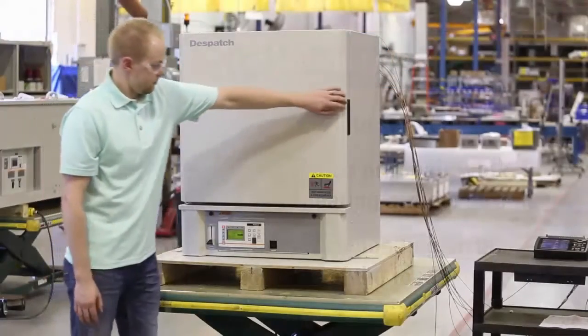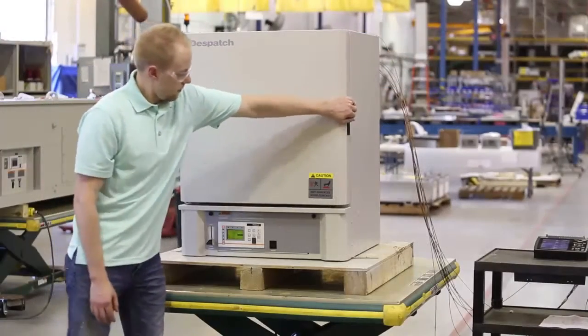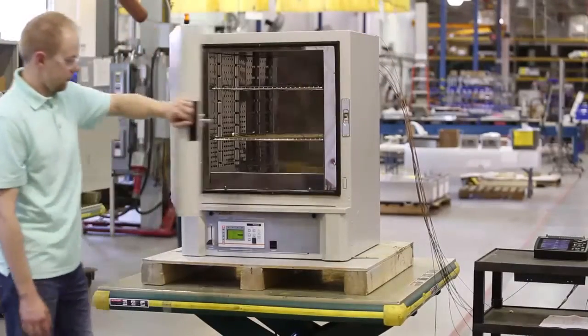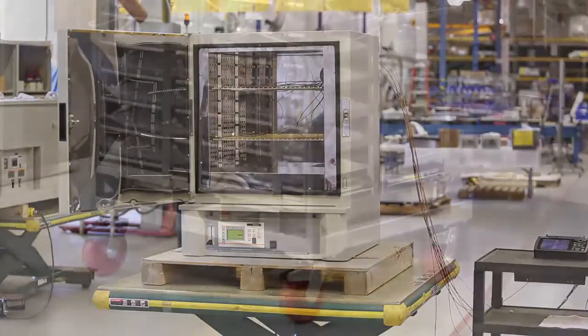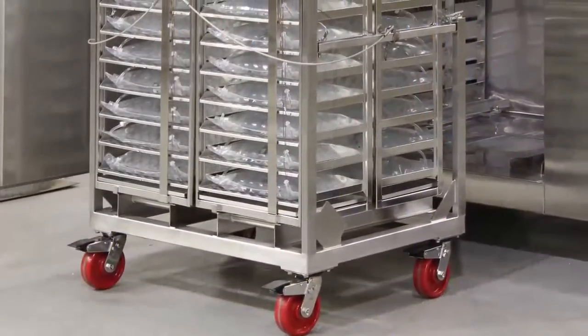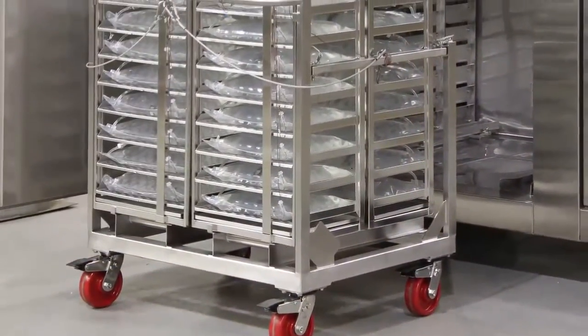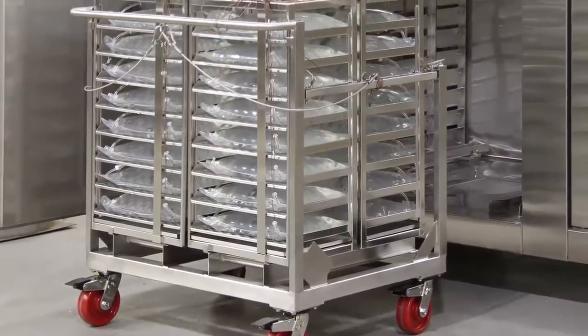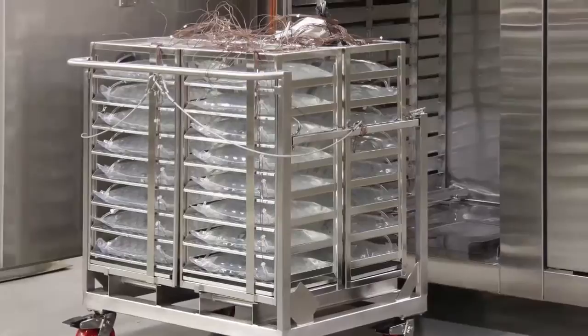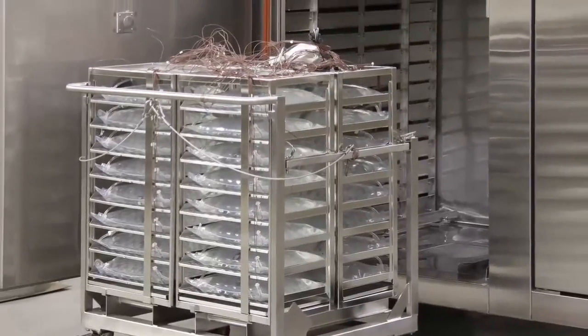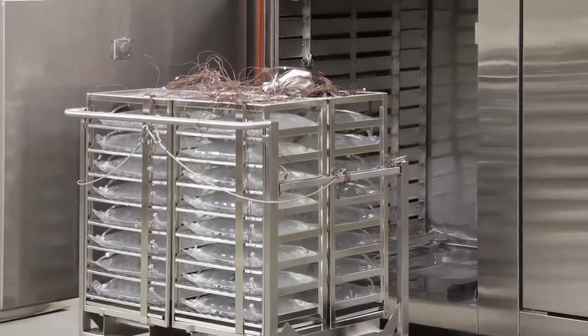The first test should be performed with no load to verify that the oven is performing to specification. A second test with product loaded should also be conducted. This test will help determine proper oven loading and airflow.